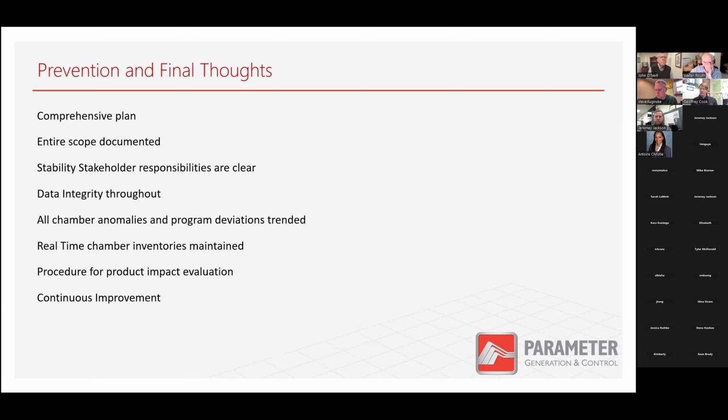And the data integrity, I went over just a little bit. We're very excited about the Ethernet connectivity. Our new controller will communicate a plethora of variables, I think something like over 35 variables, through Ethernet to a wide range of software that can interact with it. It's basically just like a set of Modbus data IP addresses that you can correlate tags to. But that will monitor all the chamber deviations. You can set the alarms.